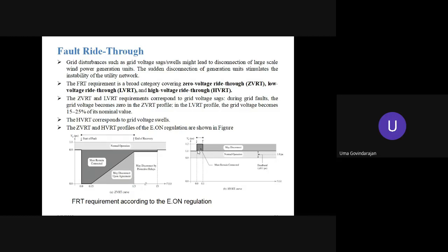When the voltage goes above 1.1 per unit, say from the initiation at t equal to 0, and stays above 1.1 for less than 0.1 seconds, the generator will stay connected. Beyond 0.1 seconds, it may get disconnected. So it is very important during grid interconnection. How to improve the LVRT capability of induction generators is a separate study.